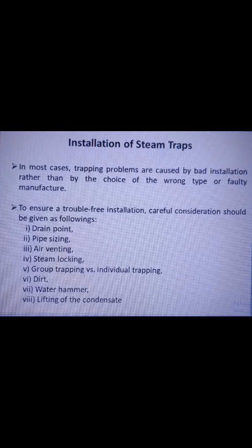Last one is lifting the condensate. In the interest of energy and treated water savings, every effort should be made to recover and reuse the condensate. Generally, this means lifting the condensate into a return main above the equipment. There may also be a case where the layout of the plant dictates that the steam traps be fitted above the equipment being drained. Wrong installation can lead to trouble because of the back pressure imposed upon the steam traps.